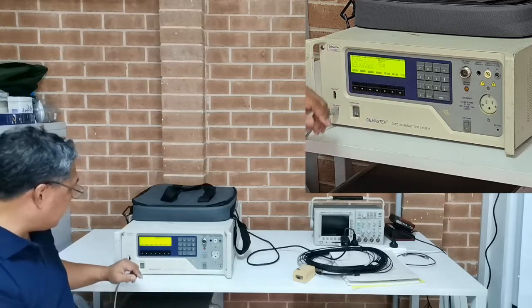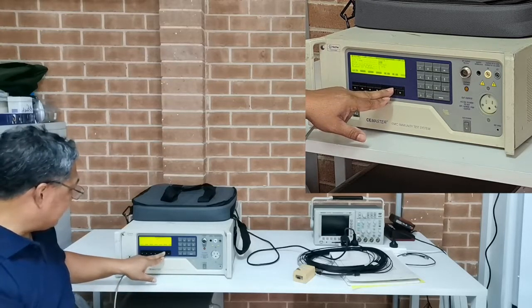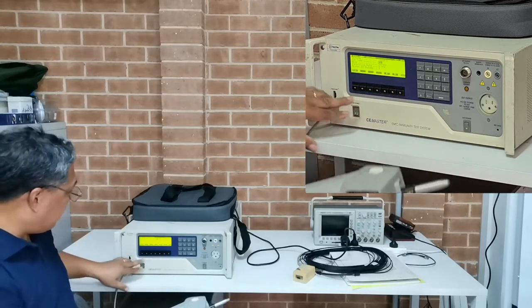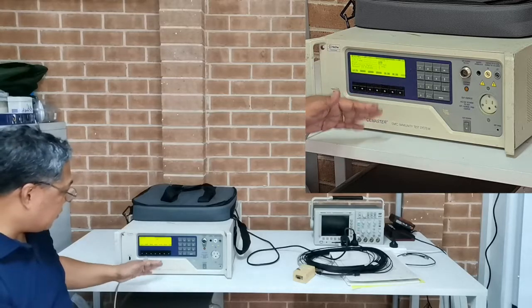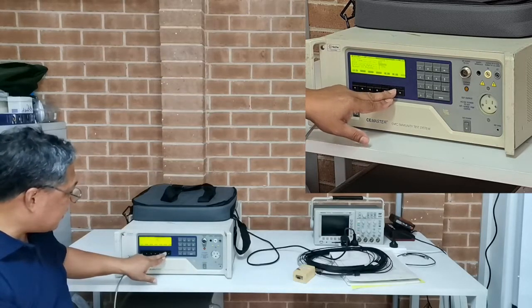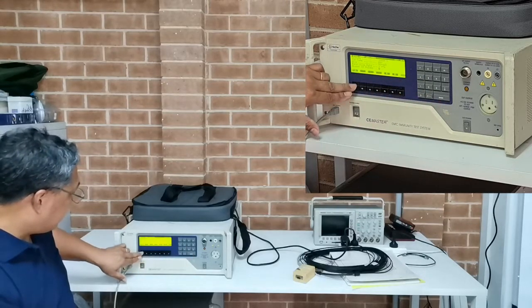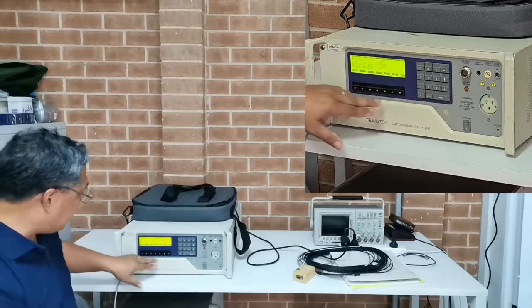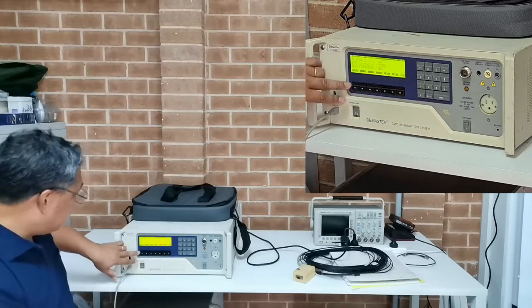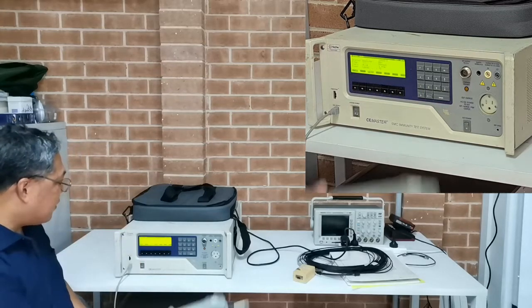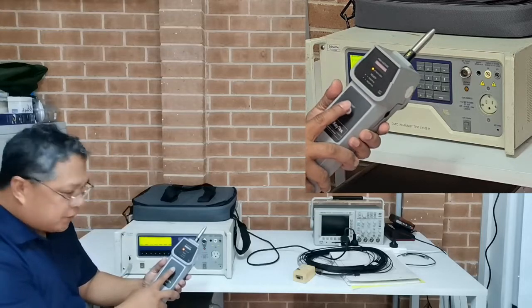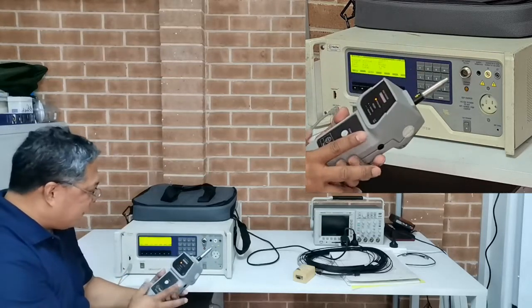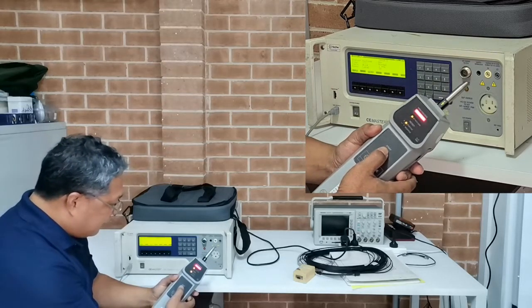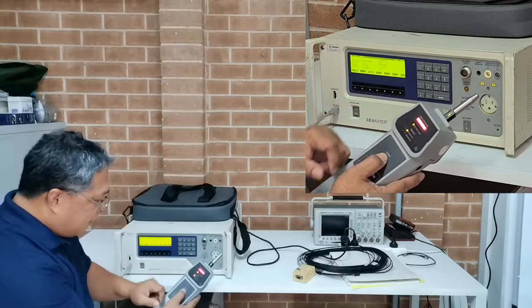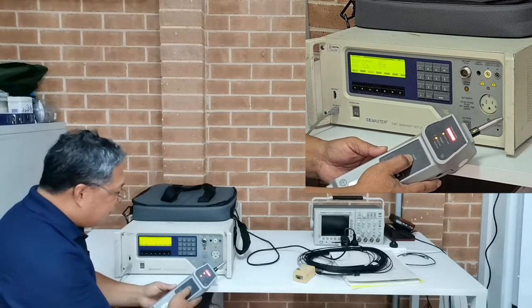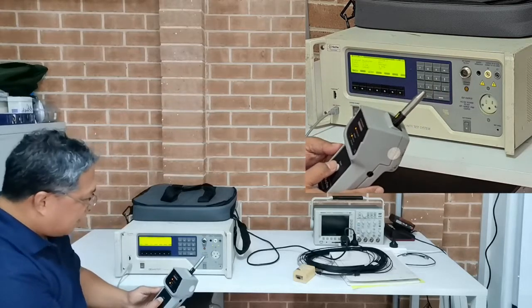So air, normal mode, and when we try, this is 1 pulse per second. And we set the number of pulses, which I'll set to 5. But normally we have to apply 10 discharges per polarity. So we'll try 10. So we'll try to run. It says waiting. So it's waiting for me to press this button, I guess, because it's the first time I have this ESD gun. So I have to press this button. Okay, it says positive and attached to ground. So we'll try this one here. Oh, you see that?